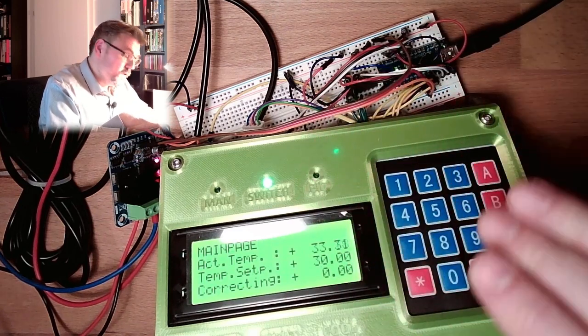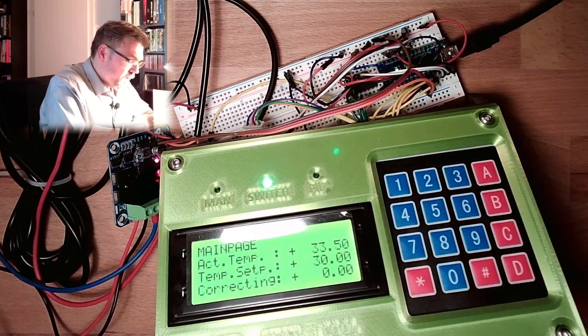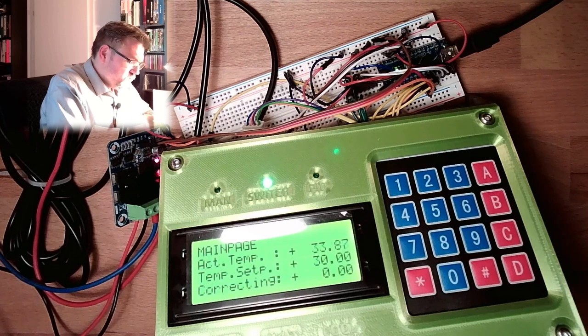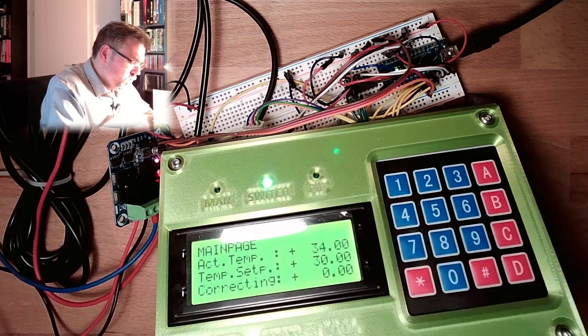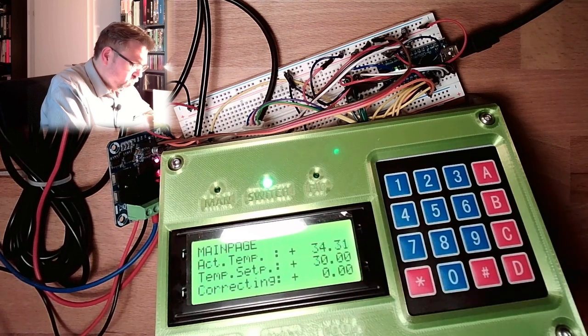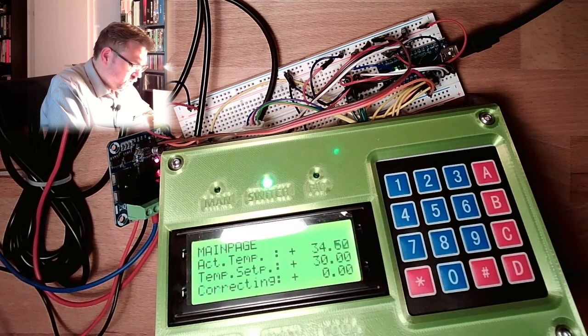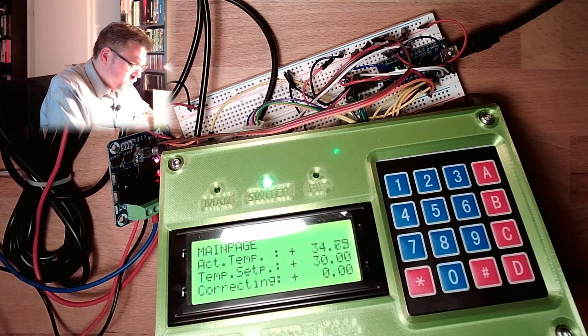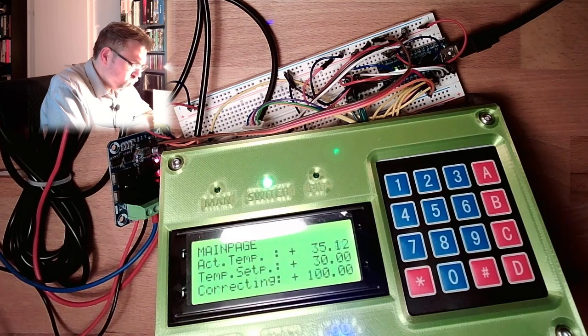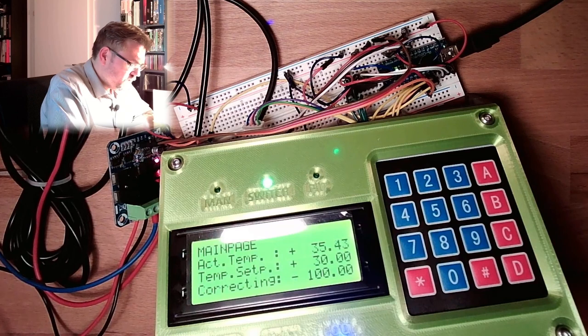And this I will set to minus 5, so the original parameters. So at 29 we should see at least the heat turning off. What was the set point? Aha, 30, alright. We've watched the wrong temperature. Yeah, so it's still rising. Now we should see the cooling turn on. Probably.